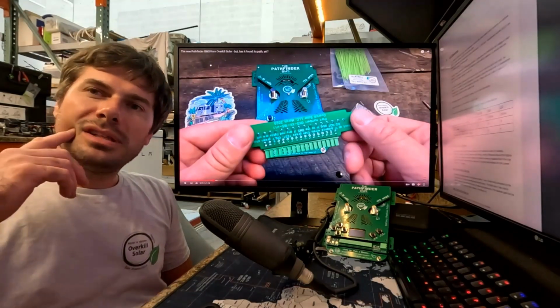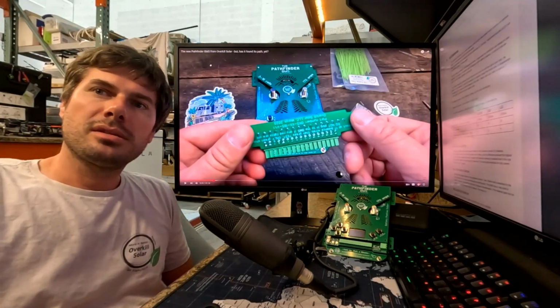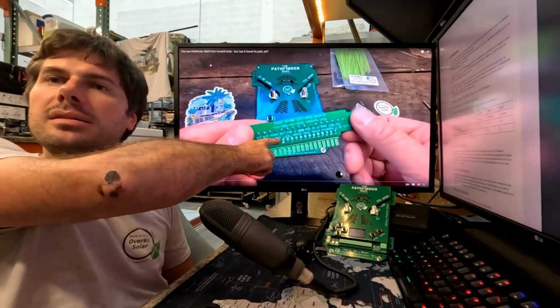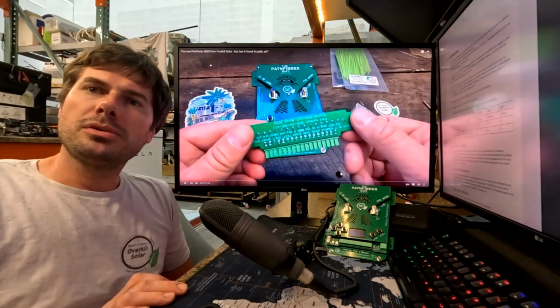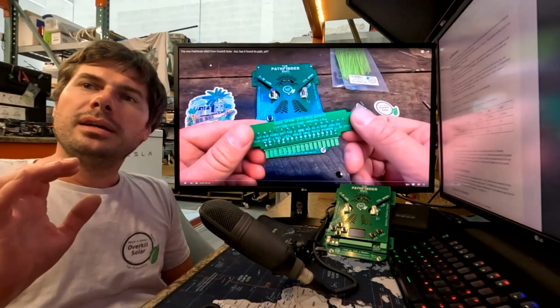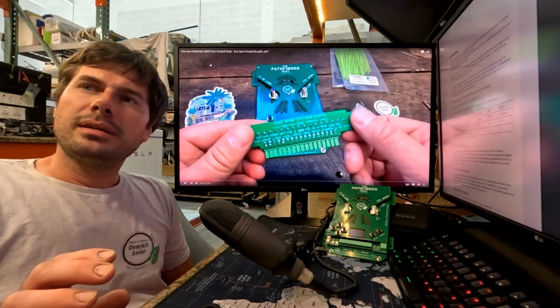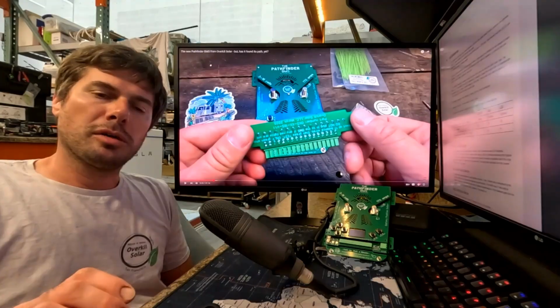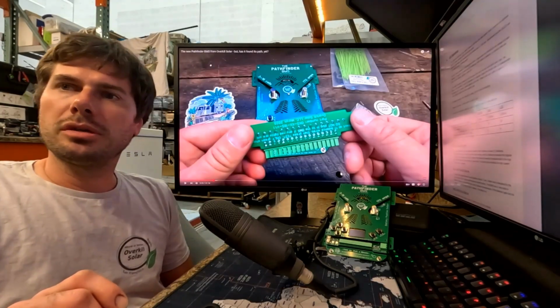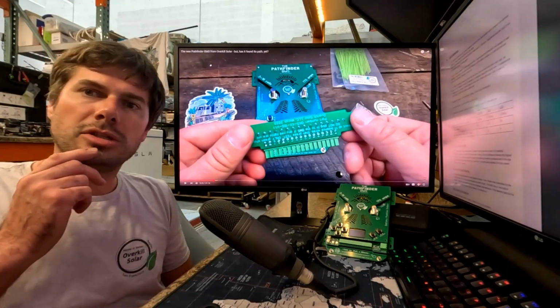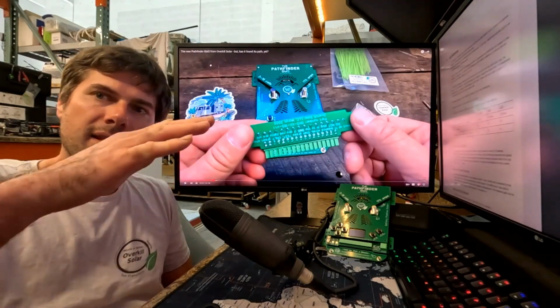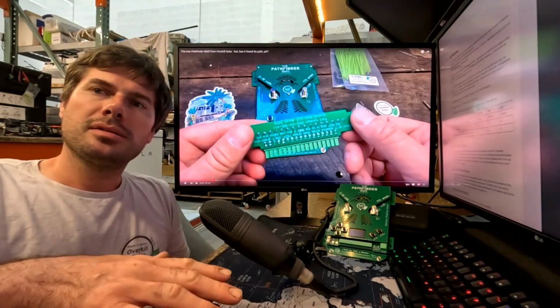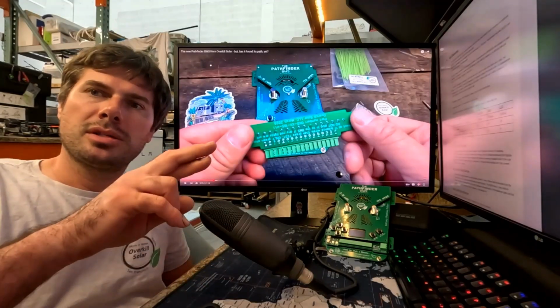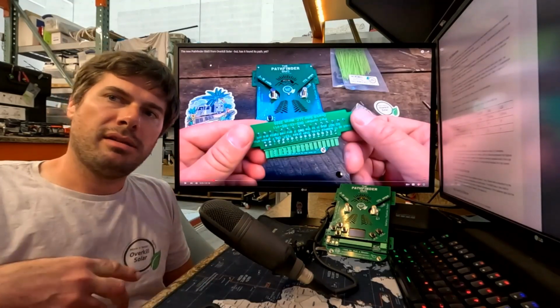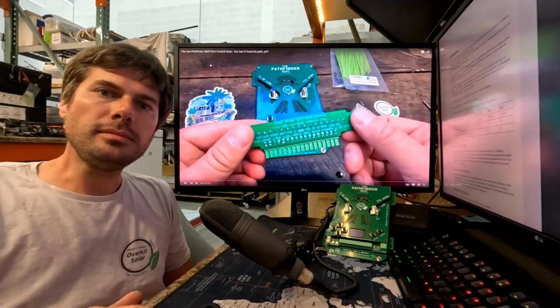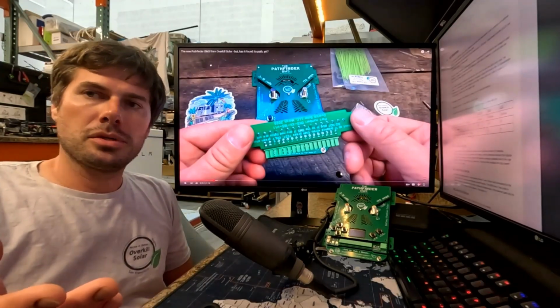The only part I still don't like about this terminal board is that the exposed connections on the bottom are vulnerable to shorting out on the workbench. I've had to replace some of these terminal boards because a customer was connecting up their wires, set the board down on something metal, crossed two wires, and that burns the traces out of the terminal board. Good news is those are cheap and easy to replace.